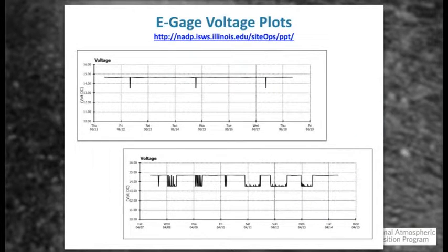Something Jeffrey can chime in on: when you submit your data, and this is if you have an electronic rain gauge, one of the nice things in our setup is the data logger is constantly logging the voltage coming out of your collector, and it should be wired that way. If you're not seeing a voltage signal when you look at the data off the website, and you're encouraged to look at the precipitation data, we actually have a note in the mailing coming out with the July data about how to get to this website. Maybe we did it last month. Yeah, we did it recently. That talks about diagnostics.